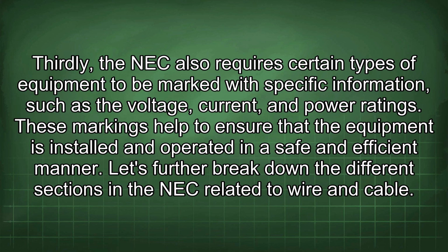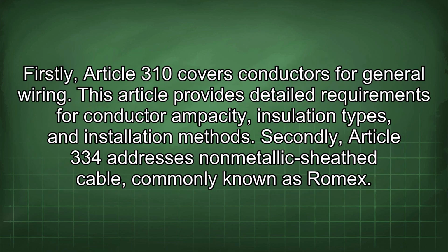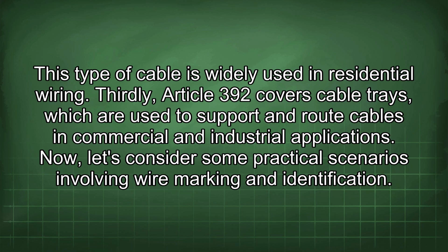Let's further break down the different sections in the NEC related to wire and cable. Firstly, Article 310 covers conductors for general wiring. This article provides detailed requirements for conductor ampacity, insulation types, and installation methods. Secondly, Article 334 addresses non-metallic sheathed cable, commonly known as Romex. This type of cable is widely used in residential wiring. Thirdly, Article 392 covers cable trays, which are used to support and route cables in commercial and industrial applications.